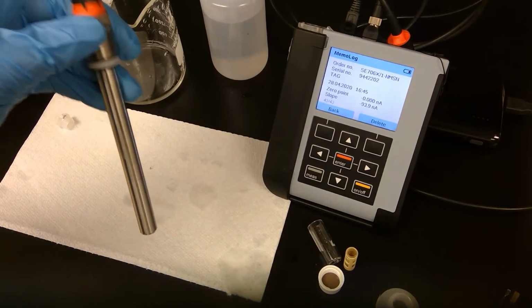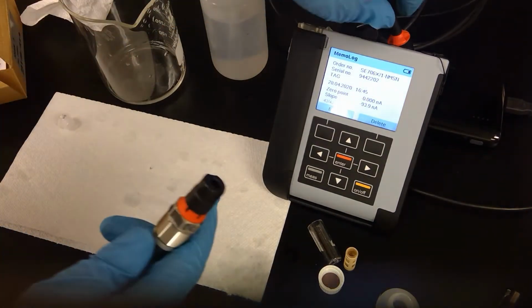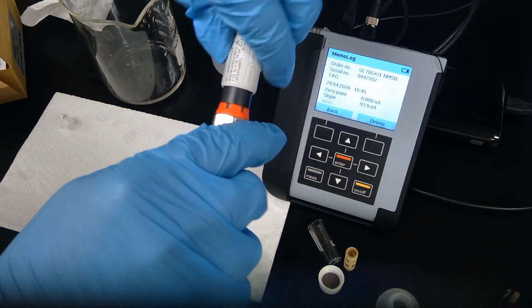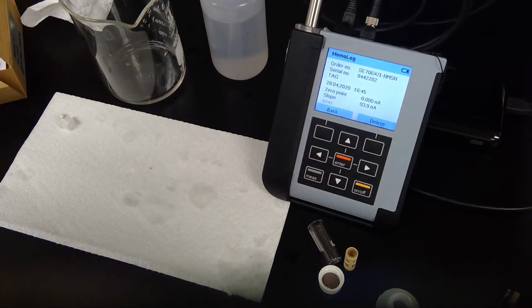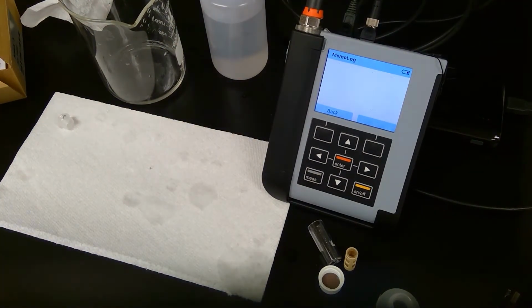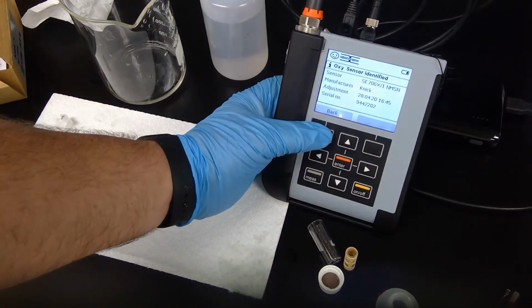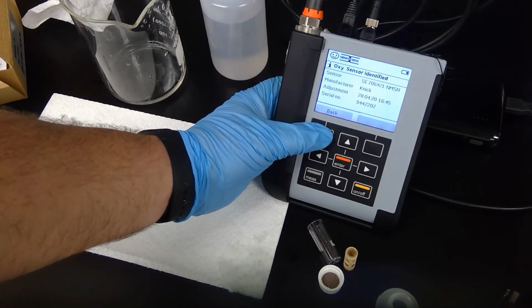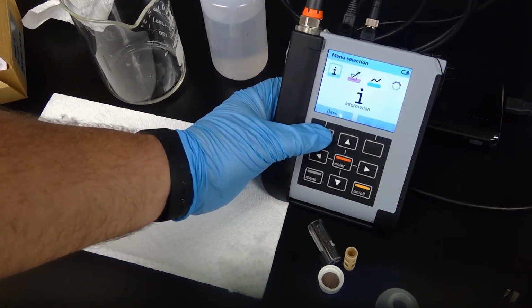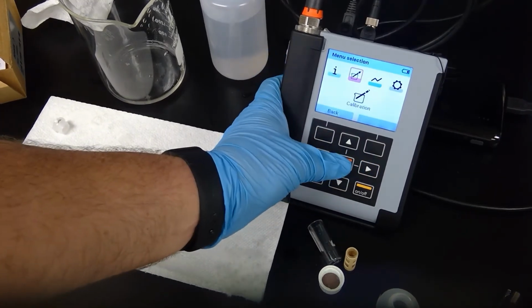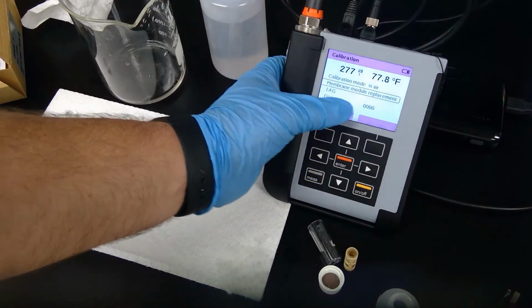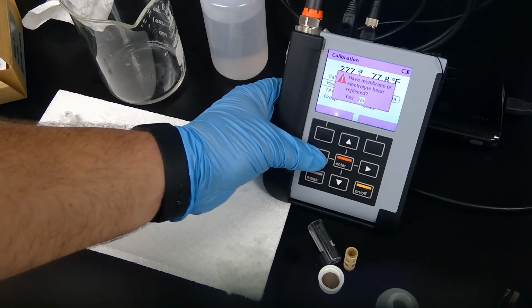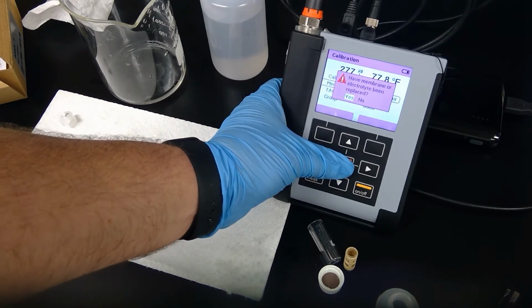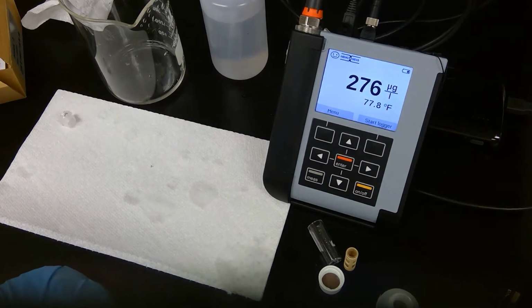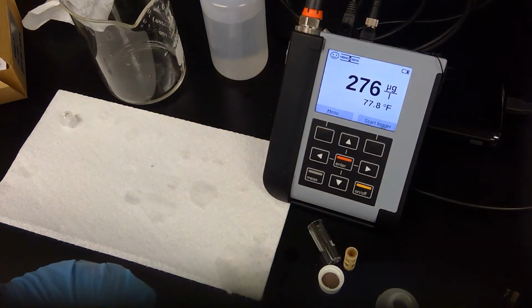Now one of the things you need to make sure you do next is connect it to the Portavo, which I have sitting here, and plug it in. And we're going to do the membrane replacement, and this resets the wear for the membrane. So I hit Menu, Calibration, Membrane Module Replacement, I hit Enter, and then I say yes, and that's it. It's very straightforward. That way the membrane wear is reset back to 0.